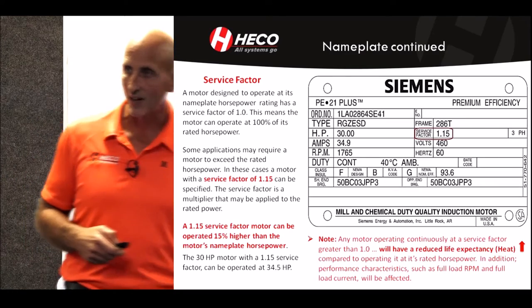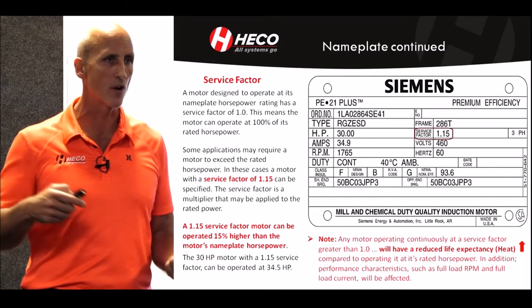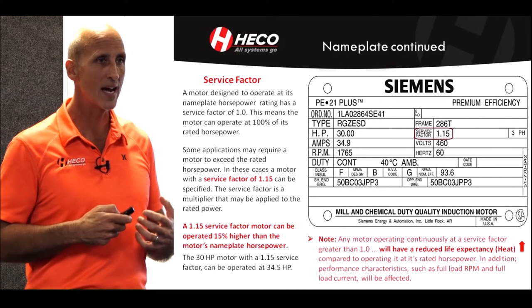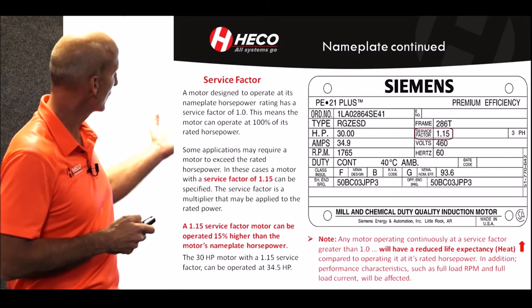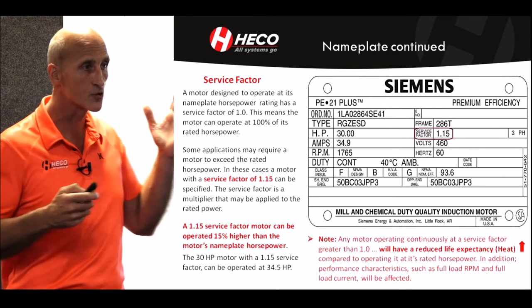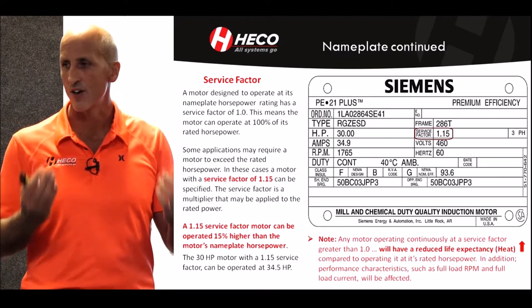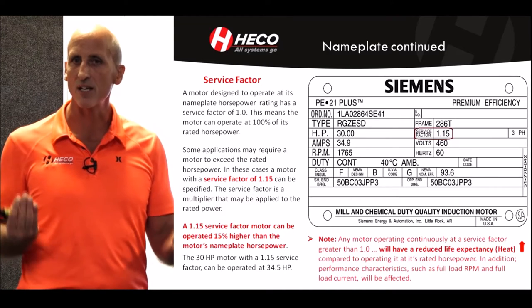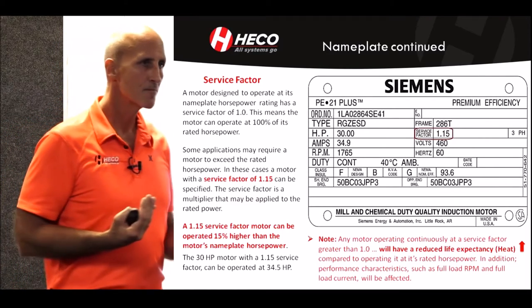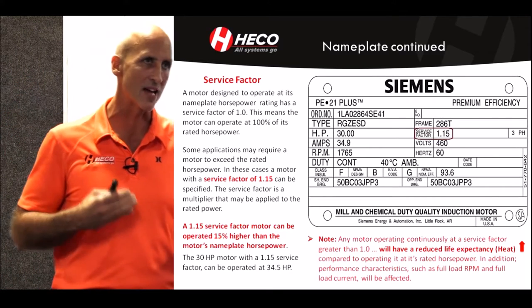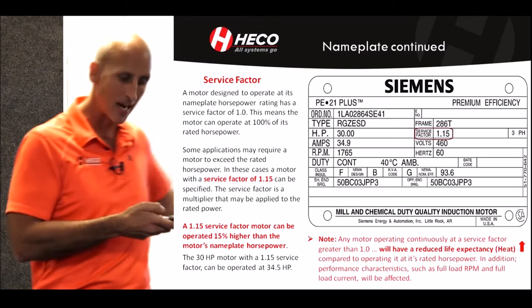Service factor is another misunderstood piece of information on the nameplate. Service factor is a multiplier that can be applied to the horsepower or to the amperage of the motor to allow that motor to be intermittently overloaded. What happens in real life is people will say, 'I've got a 30 horse with a 1.15 service factor—doesn't that mean I can just run it continuously at 35 horsepower?' No. You can, but the motor is going to run hotter. Every 10 degrees C rise in temperature of the motor winding results in cutting the winding life in half. That can also explain why some applications have repetitive failures that people haven't figured out.